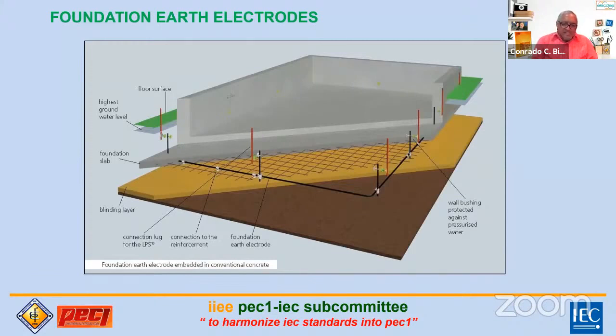So designers should be very careful not to just cite Article 2.50 of the PEC and leave it at that. We should include details so our grounding or earthing systems are properly documented, especially as-built drawings, so that during preventive maintenance or inspection we know where to go and where to look if there's a problem. It's very important to have a proper installation on the earthing, especially the embedded parts that get poured over.